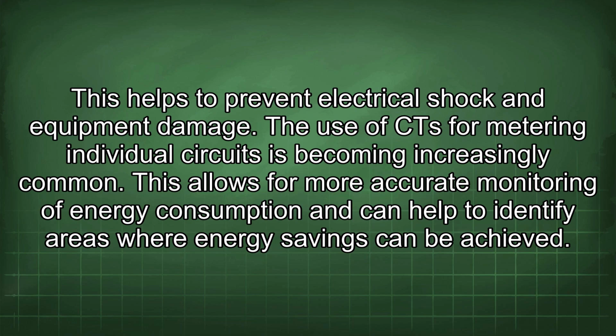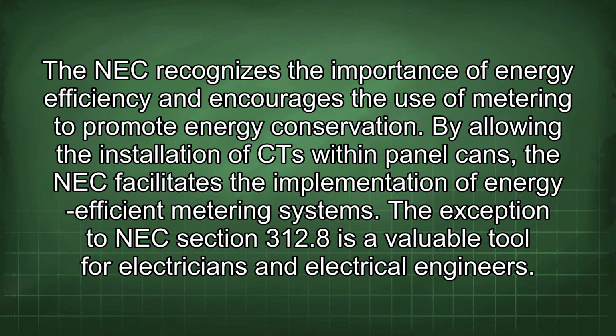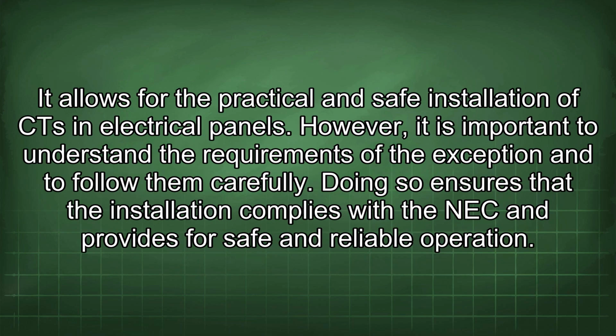The use of CT for metering individual circuits is becoming increasingly common. This allows for more accurate monitoring of energy consumption and can help to identify areas where energy savings can be achieved. The NEC recognizes the importance of energy efficiency and encourages the use of metering to promote energy conservation. By allowing the installation of CT within panel cans, the NEC facilitates the implementation of energy-efficient metering systems. The exception to NEC Section 312.8 is a valuable tool for electricians and electrical engineers. It allows for the practical and safe installation of CT in electrical panels. However, it is important to understand the requirements of the exception and to follow them carefully. Doing so ensures that the installation complies with the NEC and provides for safe and reliable operation.